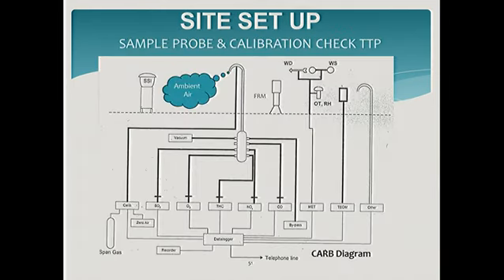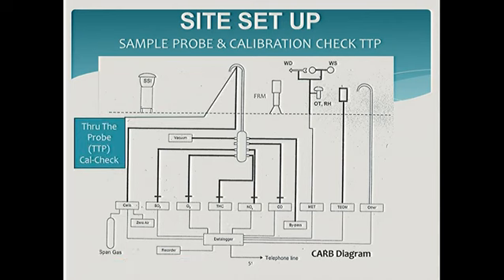All right. Okay, this is a recommended manifold gas sampling setup. What makes it through the probe cal check is the connection from the gas diluter output, sending the gas on a specific gas mix to the inlet probe. And the instruments, connected to the manifold, then pull down the gas mix to be analyzed. Okay, this setup simulates the normal atmospheric sampling conditions. And during the audits, this is the process, through the probe, that they utilize and expect to conduct.